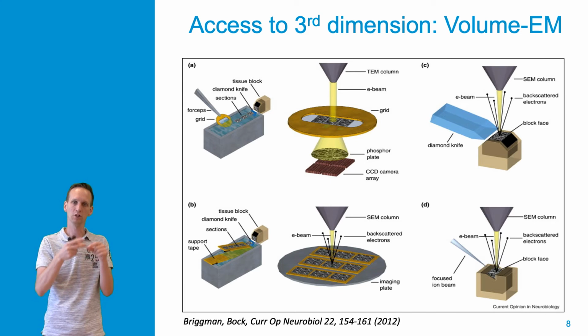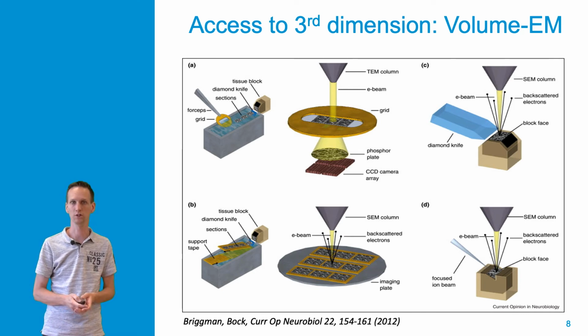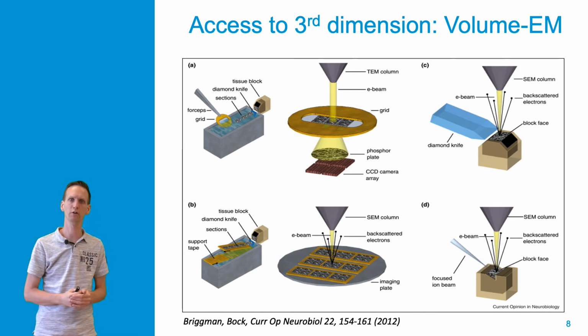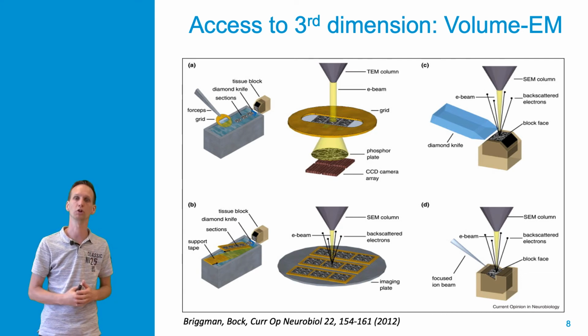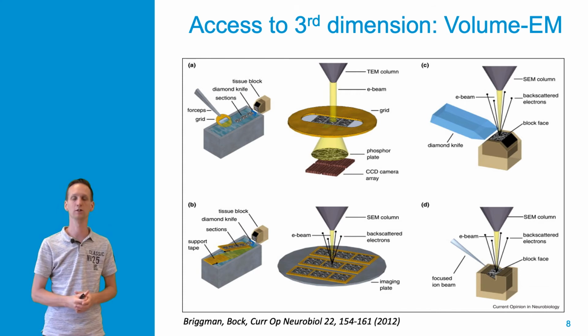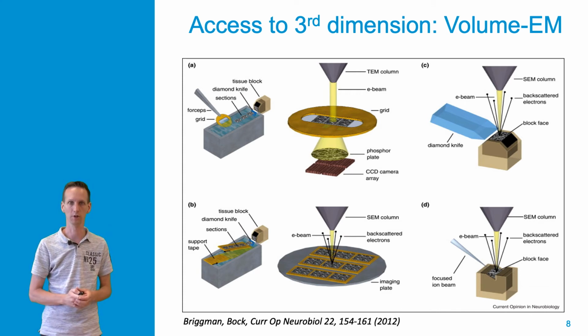Afterwards this tape can be cut into parts, stuck to a larger area, wafer or sample holder, and loaded in the electron microscope, and in this way we can load many individual sections at once in the system. There are also alternative variants that do this, for instance by adding magnetic adhesion to each section and labeling each section so that the serial order can be reconstructed afterwards, but in essence all these approaches are similar.